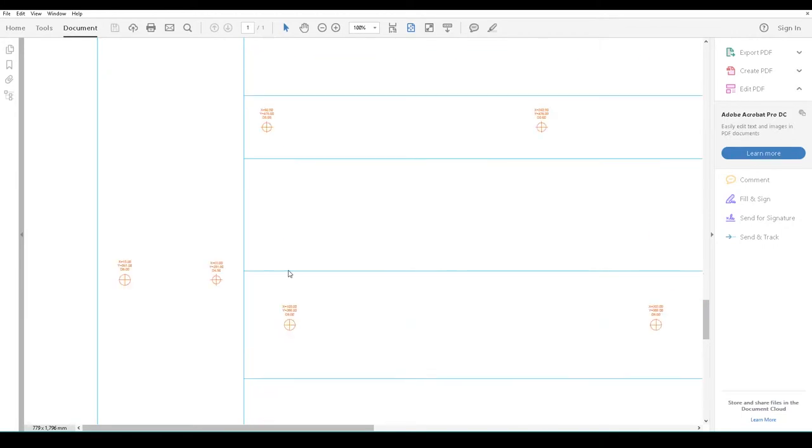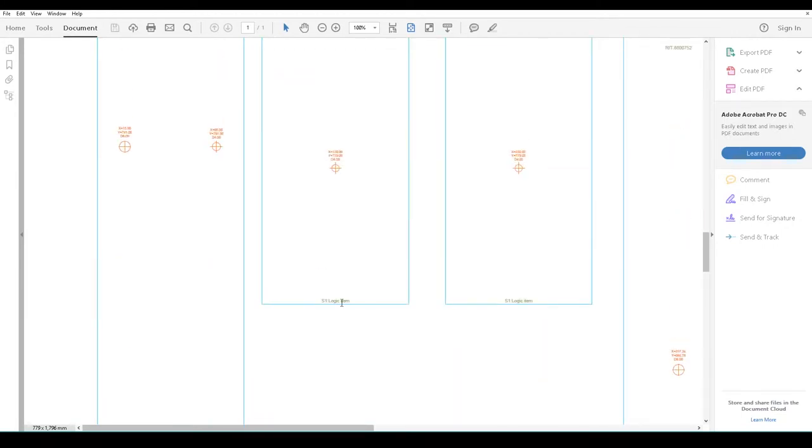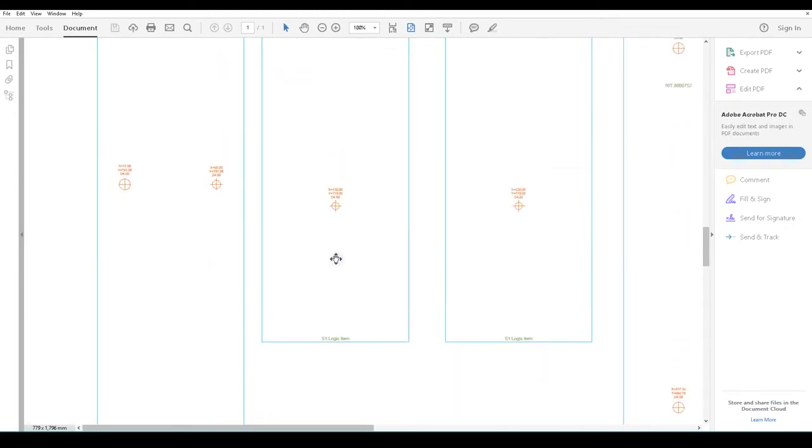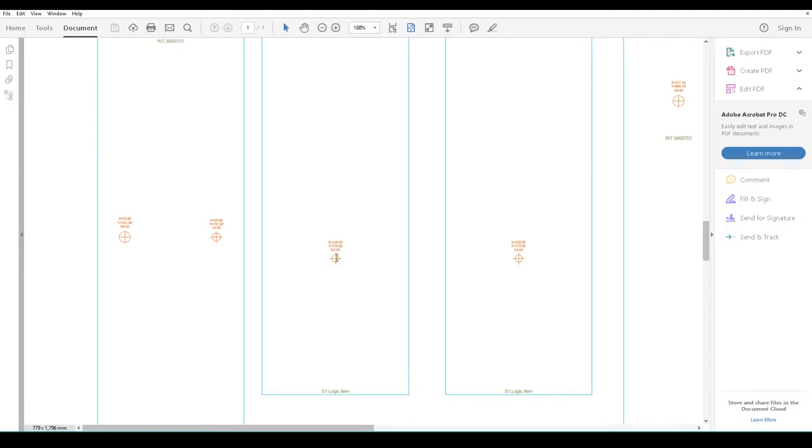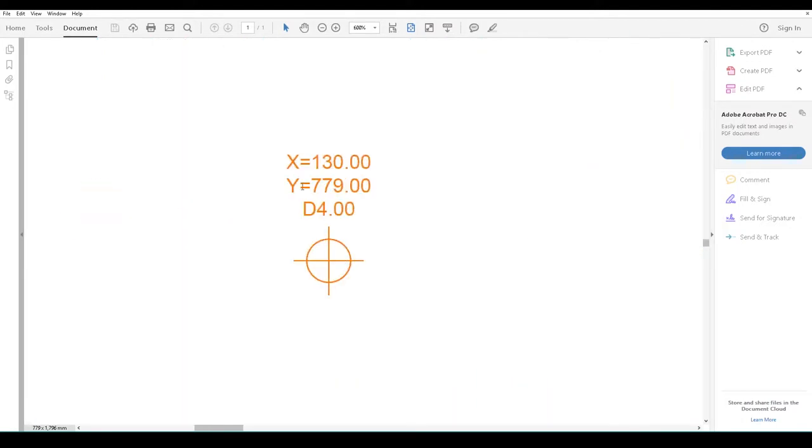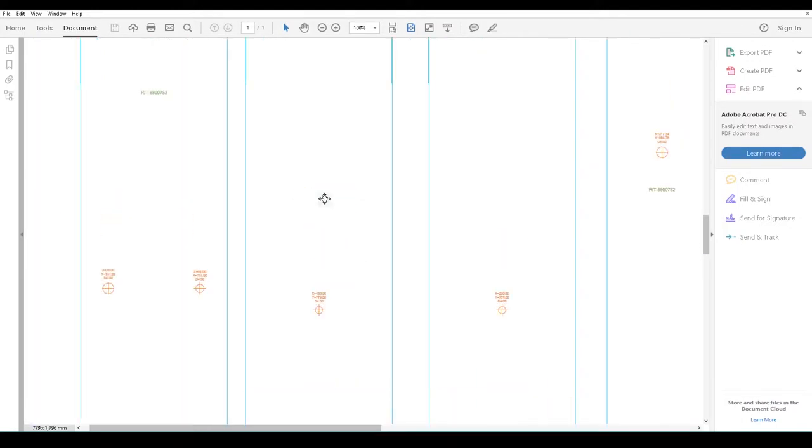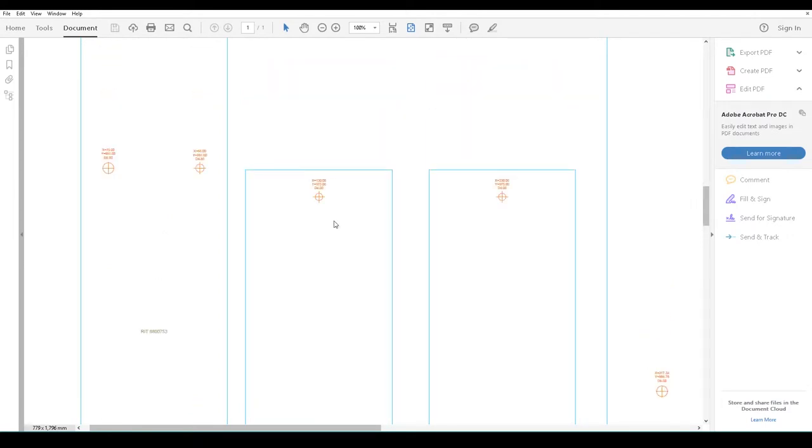If we pan over, you can see all the logic items as well. This is where we put the inverters in. You can see X130. If you plot this out to the exact size, which is perfectly possible, you can lay this directly over your backplate and drill straight through it. This reduces errors for the technicians because the panel builder and electrical engineer have given really good data they can simply grab and use.